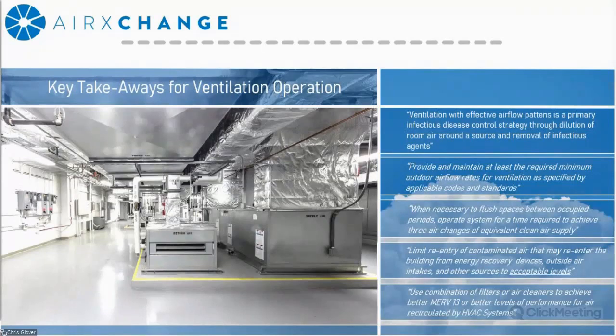Existing units operate over time and have a tendency to get less efficient, so this applies to the airflow delivery as well. If you have the ability to flush the space between occupied periods, the current suggested rate is to provide a flush equivalent to 3 air changes. Once again, this may be easier said than done for certain spaces. Limit reentry of contaminated air that may reenter the building from either recirculation or reentrainment. Keep this in mind because I'm going to discuss this in detail in a couple of further slides.